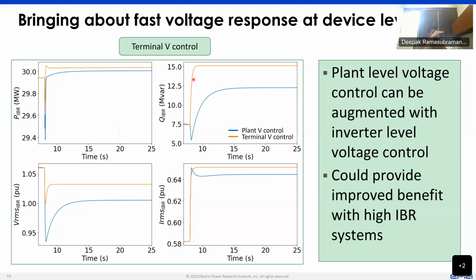Now, if you move to inverter level control, especially voltage control, then you essentially have each inverter on, let's say, the collector network of the plant, each providing some form of voltage control, which is fast. And along a power network, if you have voltage control being provided at multiple points, if they are not coordinated with each other in a reasonable enough manner, then they could fight with each other. So one of the challenges of taking this control down to the inverter level is being able to have that coordination across all the devices providing this response and still have some control at the plant level.